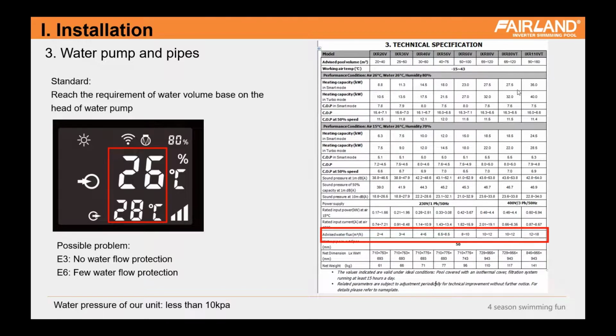And besides the cable size, another point is the water system, the water pump and pipes. Sometimes customers will ask how to choose the water pump, and we recommend the water flow volume for every unit. So when you choose the water pump, you need to consider the position, the distance between the water pump and the pool, and also their height, to choose the right water pump based on the head.